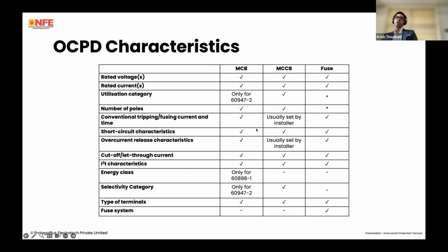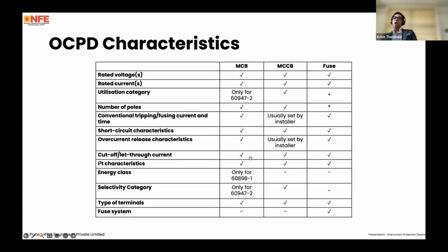We look at the conventional tripping and fusing currents and times. These are what currents cause MCCBs and fuses to blow or trip in overload conditions. For MCBs, these are defined by the manufacturer. For MCCBs, these are set by the installer on those variable tripping characteristics. And for fuses, these are already defined by the manufacturer. You also have the cutoff and let-through current. This comes through the current limiting effect of these OCPDs. These are defined for all three. I squared t, let-through energy characteristics: how much energy is let through before the device trips or fuses? These are obviously defined for all three. Energy classes are a simplified approach to let-through energy characteristics. These are only for 60898 Part 1 MCBs.